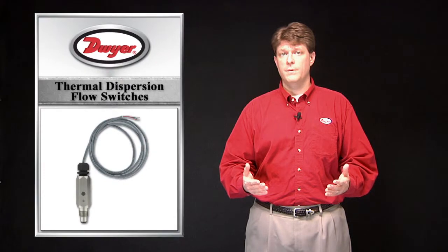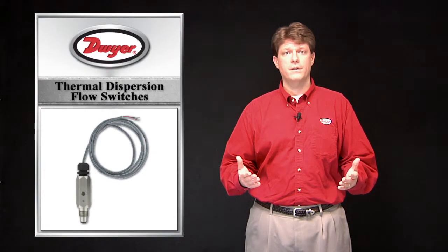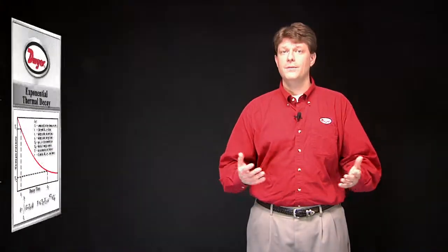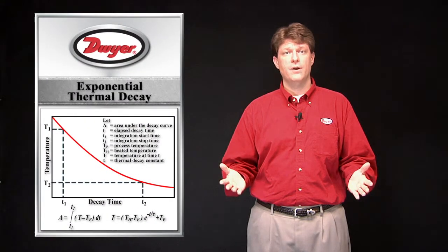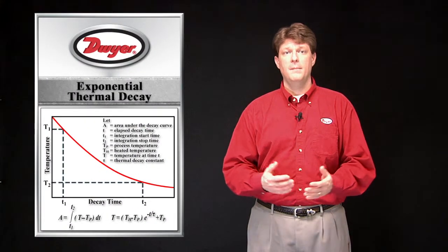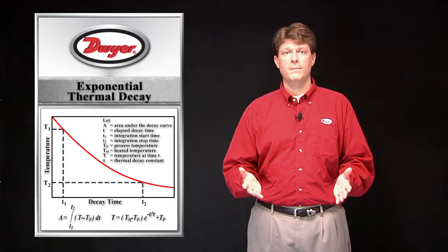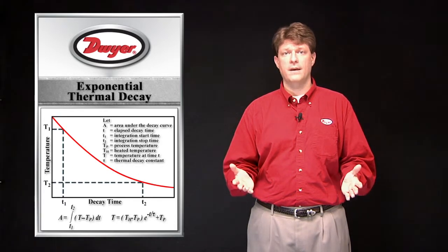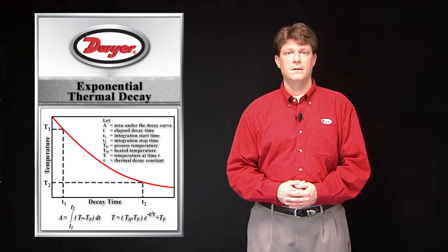Dwyer Instruments offers several flow measuring products that use a thermal sensing element. Thermal dispersion flow sensors use a temperature element that is heated up beyond the media temperature. Based on calorimetry, the flow moving past the sensor will have a cooling effect that is directly proportional to the flow velocity.